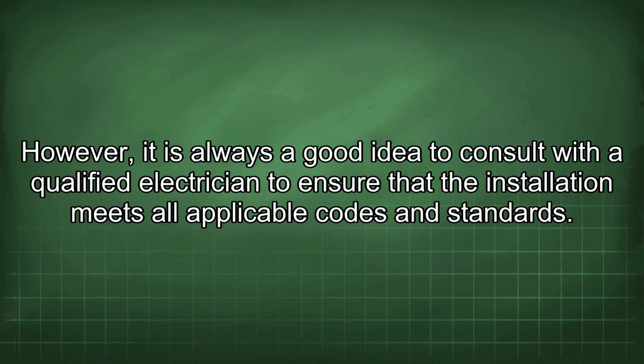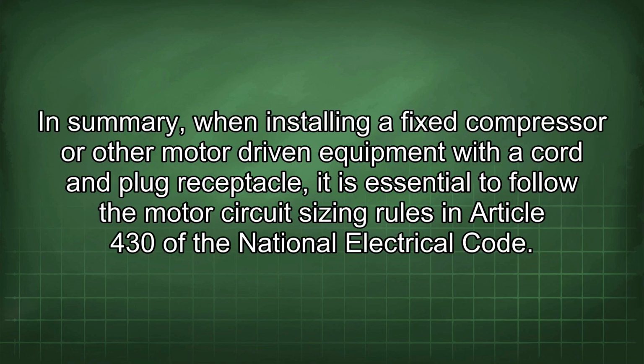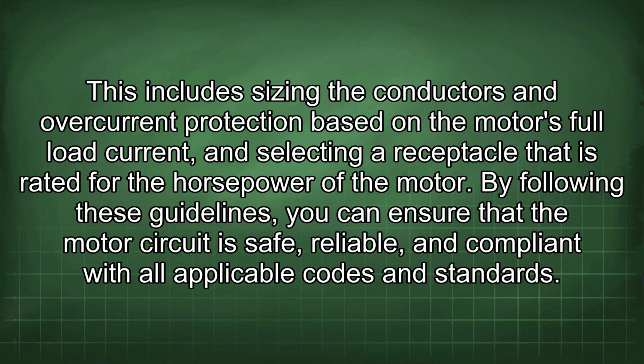In summary, when installing a fixed compressor or other motor-driven equipment with a cord and plug receptacle, it is essential to follow the motor circuit sizing rules in Article 430 of the National Electrical Code. This includes sizing the conductors and overcurrent protection based on the motor's full load current and selecting a receptacle that is rated for the horsepower of the motor. By following these guidelines, you can ensure that the motor circuit is safe, reliable, and compliant with all applicable codes and standards.